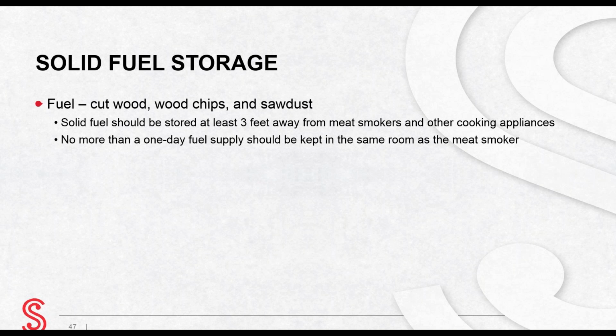solid fuels. What if you have more than 1 day's supply of fuel? It is acceptable to store that in the building if the sprinkler system allows it under NFPA 13, or against an exterior masonry wall, or outside the building 10 feet away.